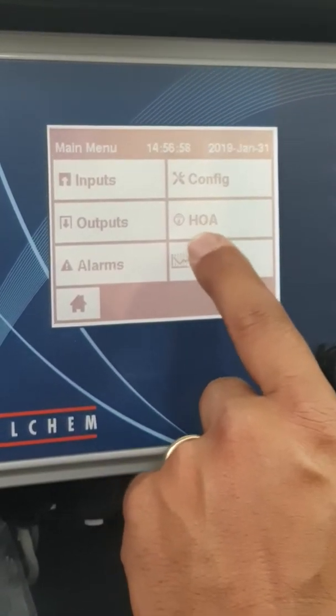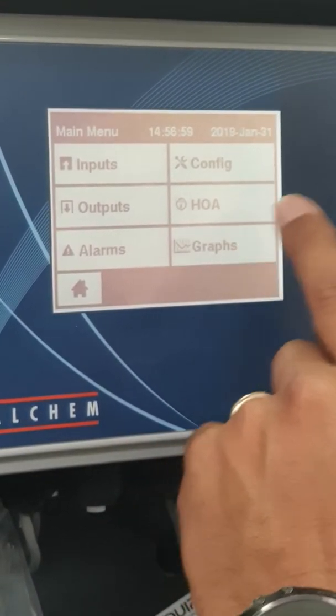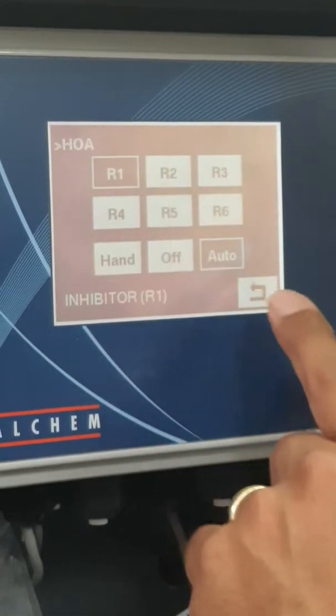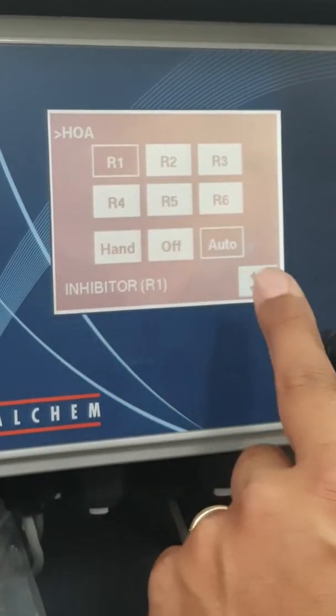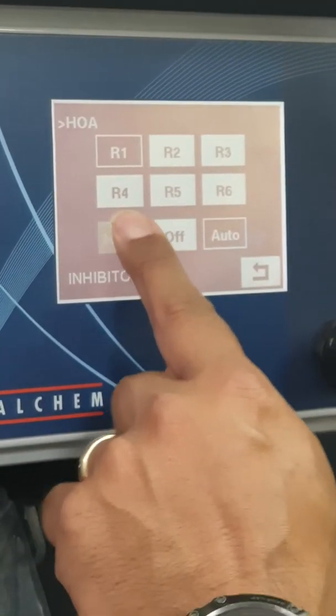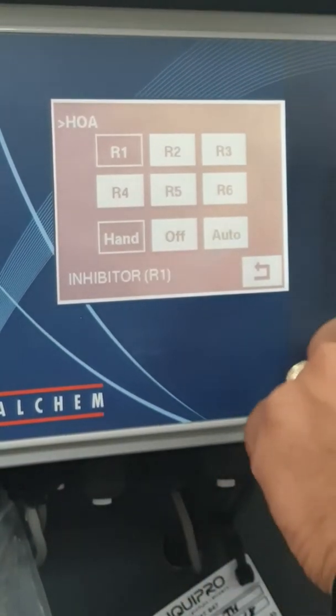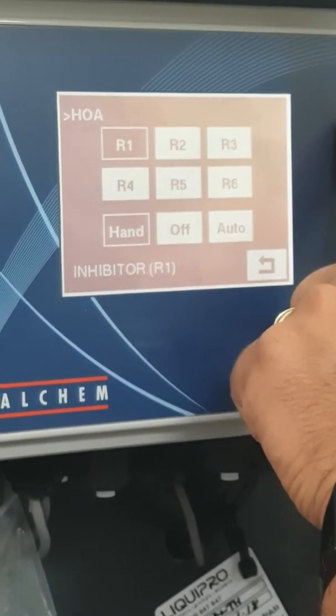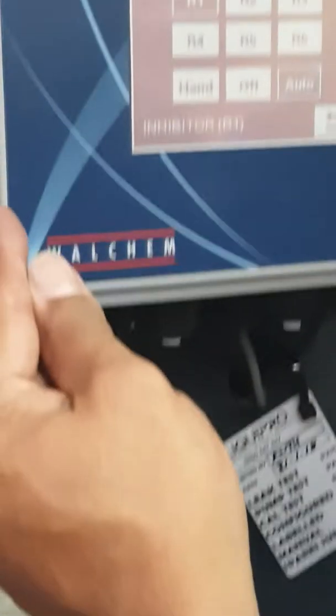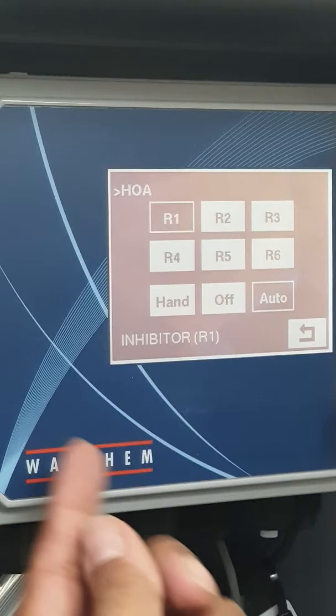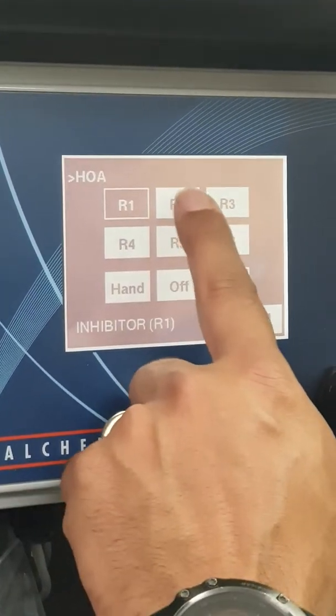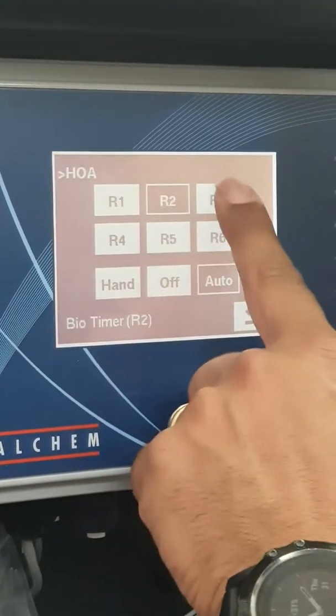HOA stands for hand, off, or automatic. It's basically a quick key to get to your relays. I could manually turn a relay on — you can see the light is now on. Off turns it off, and auto means run automatically via whatever set points you've got configured. You can do that with each relay.